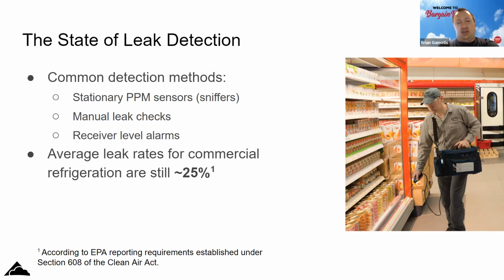We use all three of these modes here at Grocery Outlet, but each one has its pros and cons. There are limitations to each. One thing I've heard recently related to COVID is the Swiss cheese approach, where you layer on multiple imperfect solutions, trying to catch as many leaks as you can. So it sounds like the PPM sensors are good, but they're not always in the right place. Typically they're only in the machine room or maybe in the return air. And then they break frequently.